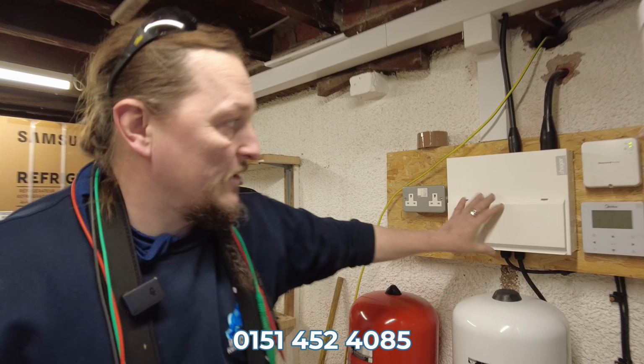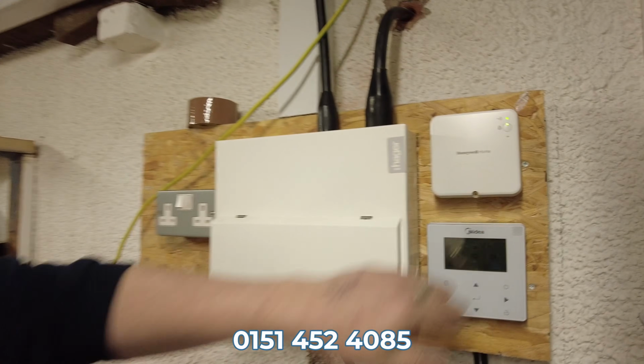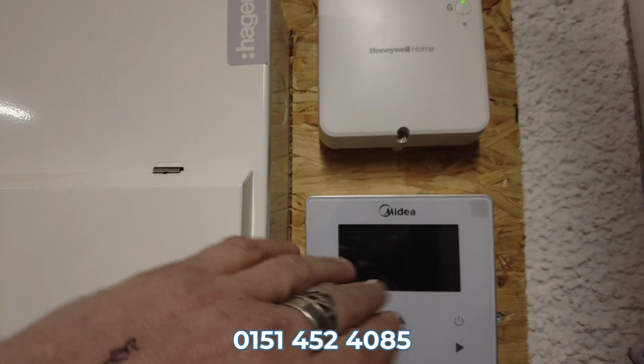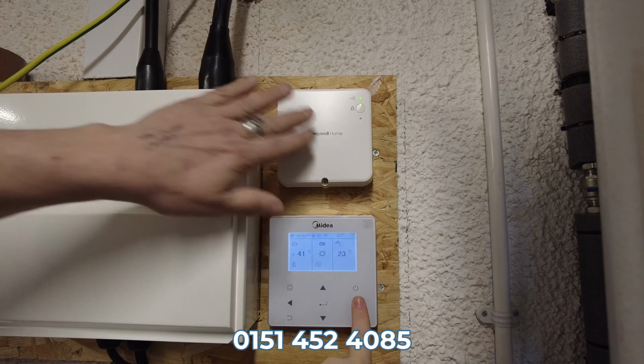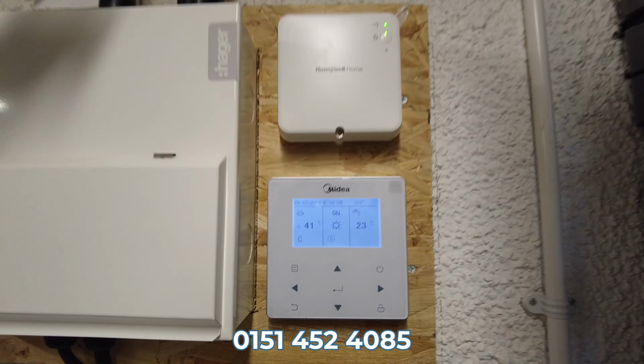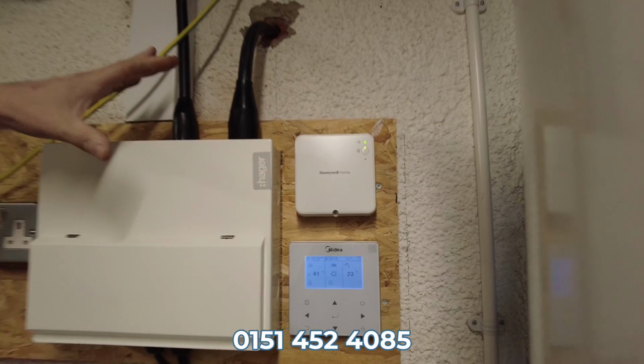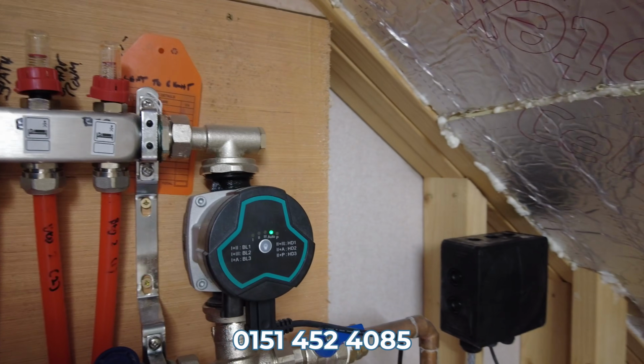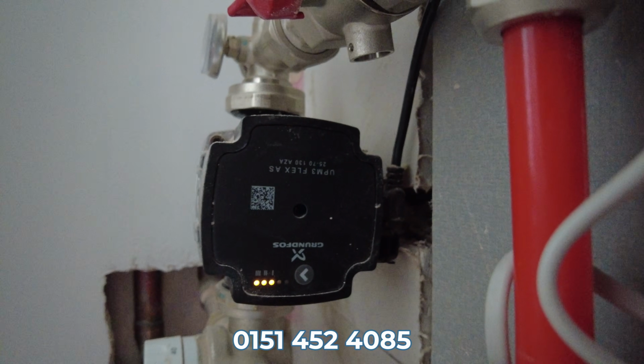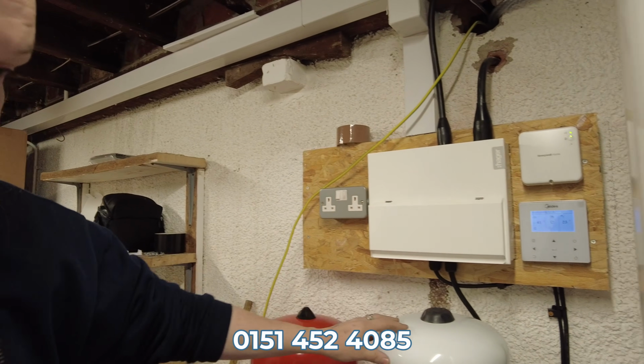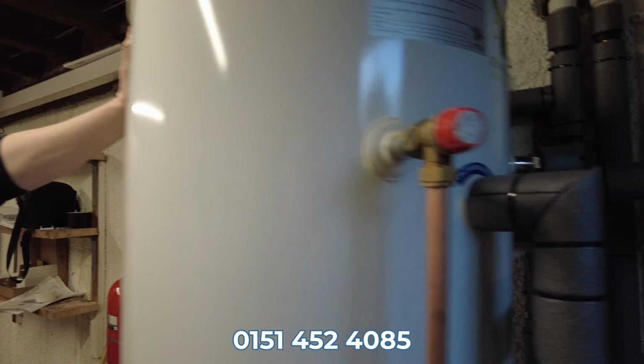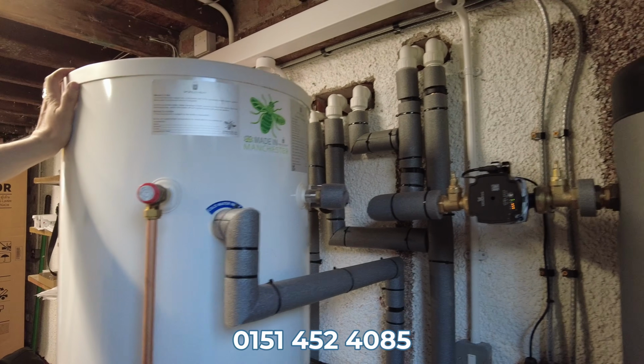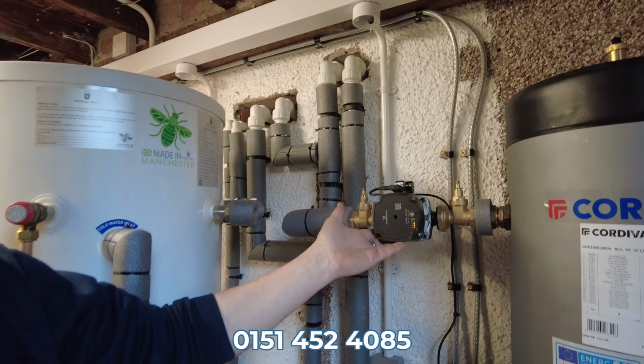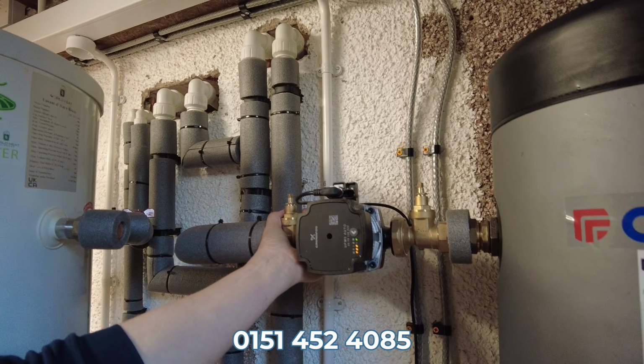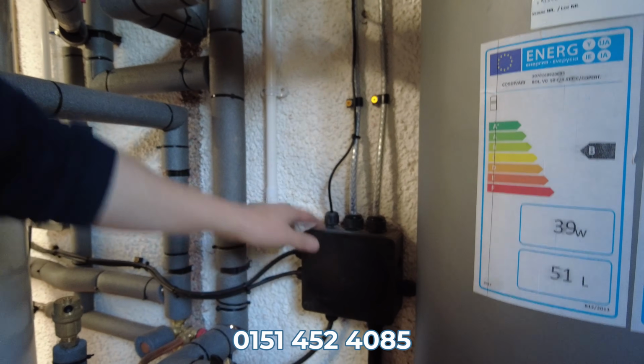We've got the power, the Midea controller, the settings for the hot water and the flow rate for the underfloor heating. We've got the temporary thermostat until the customer gets his own thermostat that's going to control all the different underfloor heating loops. But for now, we're just getting the whole house warmed up. Expansion vessels, hot water tank that's now toasty warm. As you can see, the heating pump's on and the pipes are nice and warm.